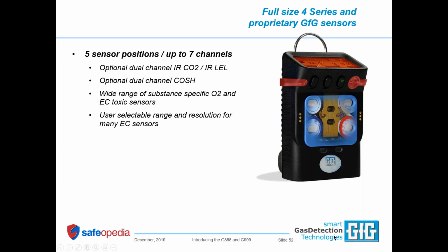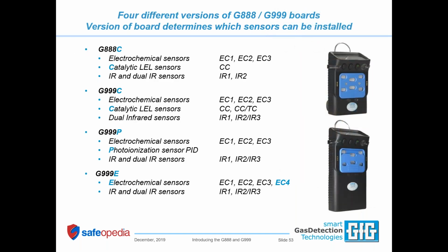In the 888 and the 999, we have positions for 5 sensors. You'll notice the center position is taken up by the IR sensor. The IR sensor is long, rectangular, and the shape and length of the sensor really do matter. Our IR LEL sensor has nothing to do with the low power IR LEL sensors turning up in some of the compliance devices being sold out there, which I don't believe many customers actually understand the limitations of. But more about that in just a couple of slides.